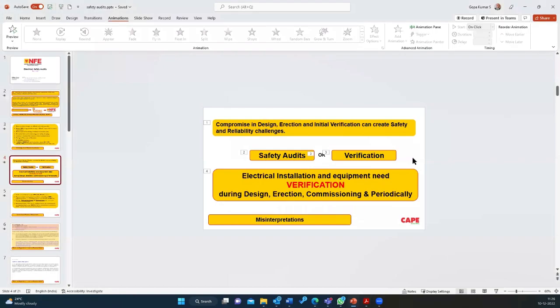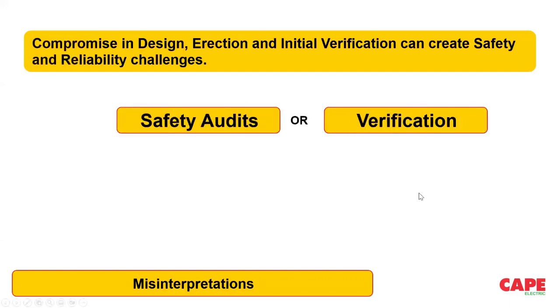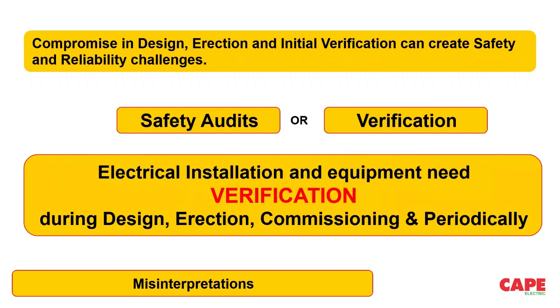So basically what I wanted to tell you is that the word audit is actually not applicable for an electrical installation. Instead, what we have to do is verification. Audit is a sampling process. A chartered accountant makes an audit. He doesn't go through the entire accounts; he checks on a sampling basis. So whatever we do on a sampling basis can be called an audit, and whatever we do thoroughly is verification. For example, fire safety: it's not fire safety audit, it is fire safety verification. So please refer to the necessary standard. You will be able to understand the meaning and the complications of this particular standard.